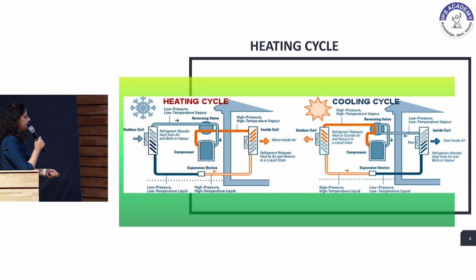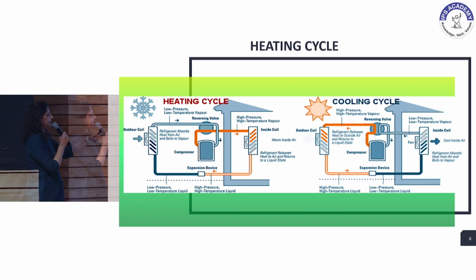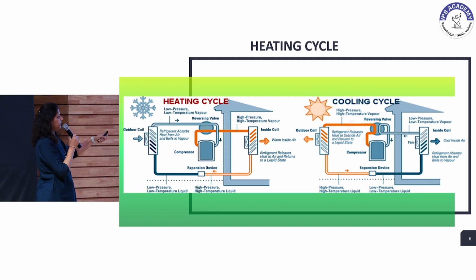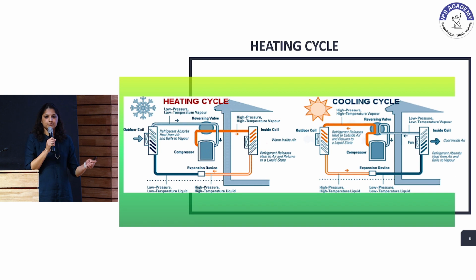Here we see the two types of compression cycles, a heating cycle and a cooling cycle. The heating cycle is completely the reverse of a cooling cycle. In a cooling cycle, vapor is compressed and the compressed vapor comes to the condenser. Through the expansion valve, it goes to the evaporator and goes back to the compressor. This is the cycle which is operating. Here we get the cold water or cold air through the evaporator. In the heating cycle, it is completely opposite. You get heated air or heated water from the condenser, and as a byproduct, you get cold air or cold water from the evaporator.